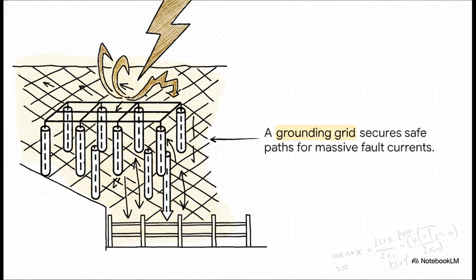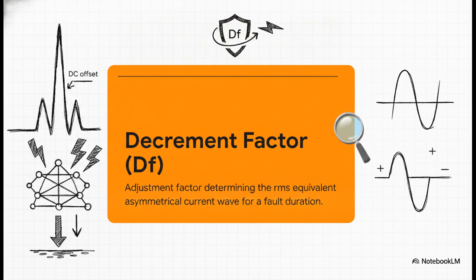But this isn't just burying wire in the dirt. It requires some intense mathematical modeling governed by the IEEE 80 standard. Because here's the thing, real faults aren't perfectly clean symmetrical waves. When a fault strikes, it often carries a sudden, massive, unidirectional spike called a DC offset. To make sure the grounding grid doesn't literally melt in those first few critical milliseconds, engineers meticulously calculate something called the decrement factor. This accounts for that deadly asymmetrical voltage spike, ensuring the grid can survive the absolute worst-case surge scenario.